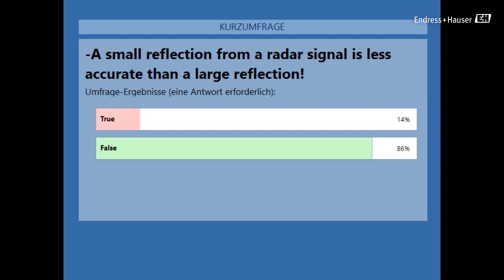You might think: I got a huge reflection, a huge signal, so it must be accurate. Always question that, because how a sensor behaves once built into a tank differs from when it was calibrated in the factory, with regard to how fast the radar propagates inside the tank. A tank may be smaller, with walls closer to the measuring rod than during calibration, and all that affects accuracy. You get huge reflections, but always set it up properly in a tank or bypass when you apply the unit. Do not just stick it in and walk away. It works, but you don't know if it's truly accurate.